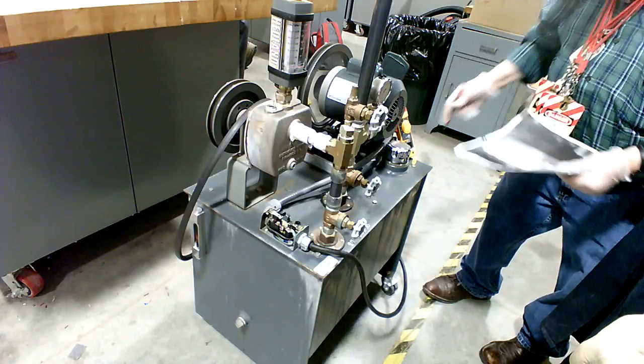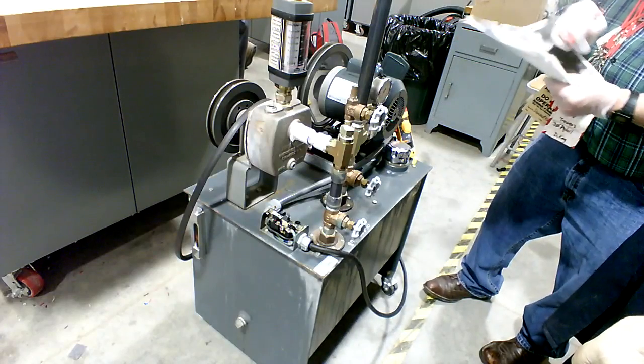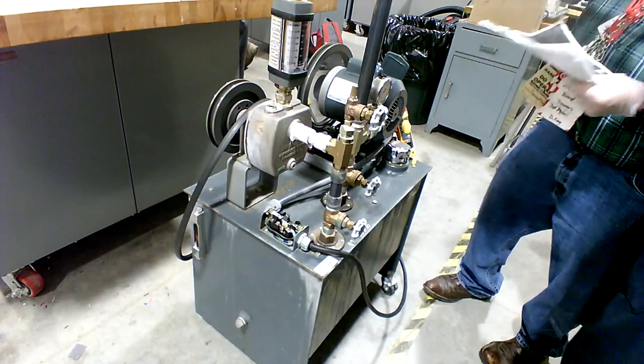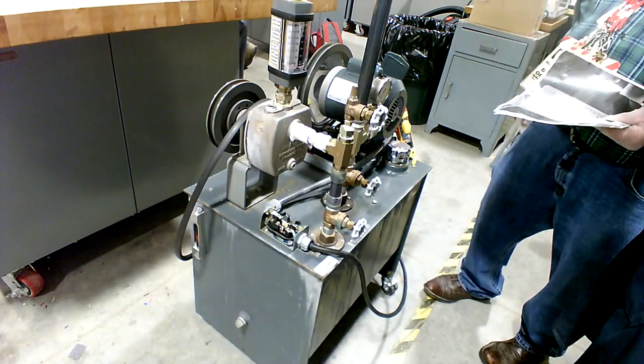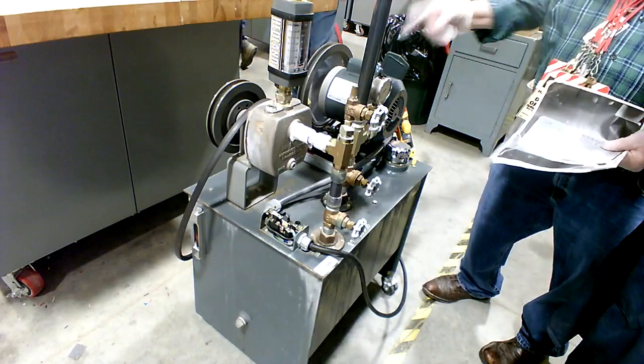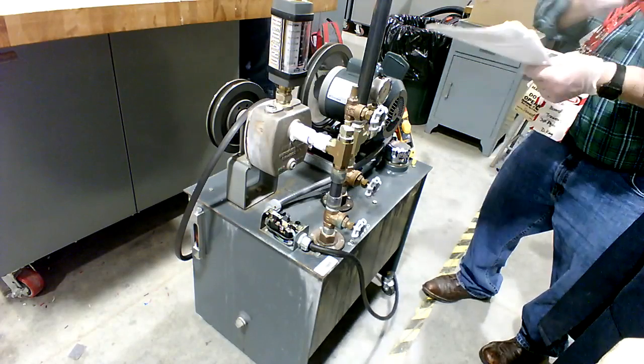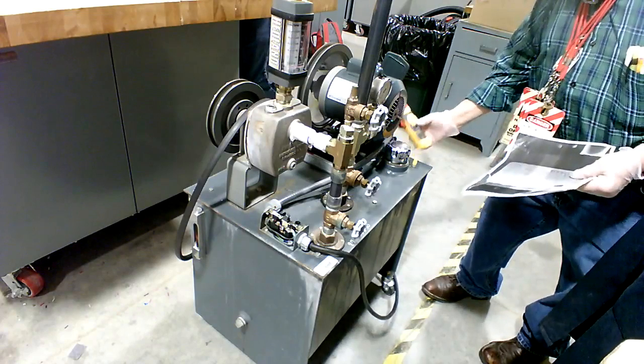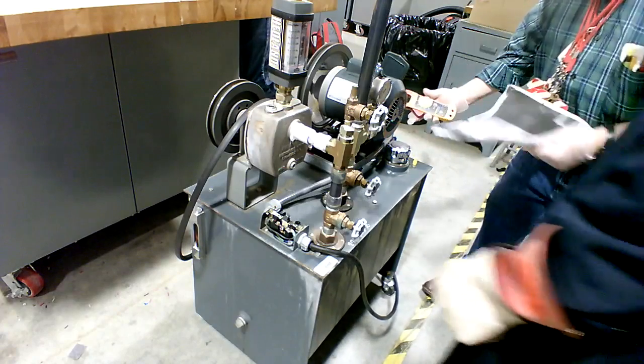If we start it, you're going to see the amps go up super high, around 38 amps. It'll go high just for a few seconds and come right back down. That's the inrush it takes to get the motor going. Even though it's at a standstill, if you cut the switch on, watch the high stroke. 35 amps, then it comes down to 7.3. That 35 was the inrush. That was the inrush current. So we talked about that in chapter 1.